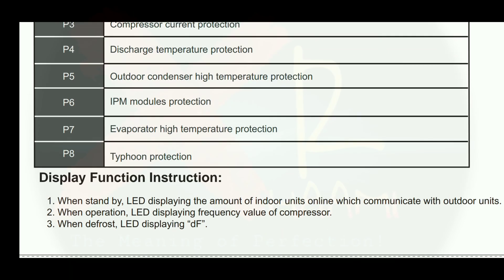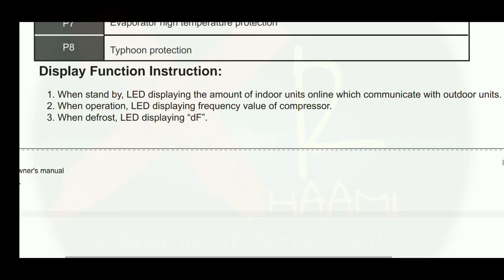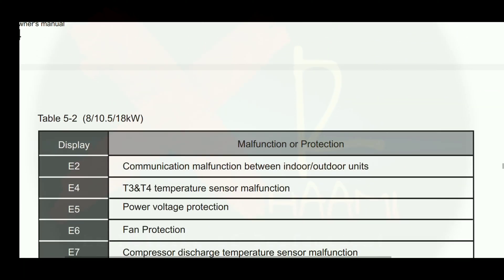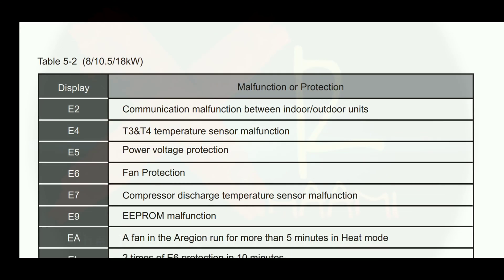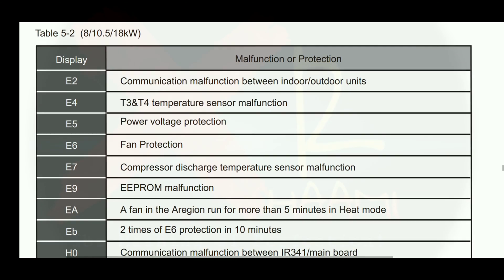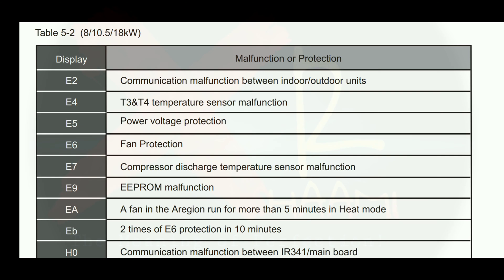Let's see the display function instructions. When the air conditioner is on standby mode, the LED displays the number of indoor units online which communicate with outdoor units. In operation mode, the LED displays the frequency value of the compressor, and during defrost, the LED displays DF. Note: this table is only for 8, 10.5, and 18 kilowatt air conditioners.